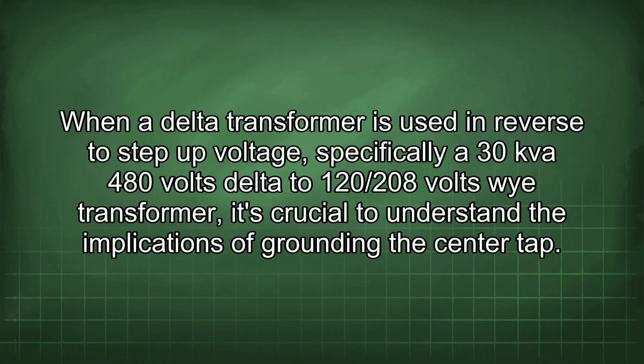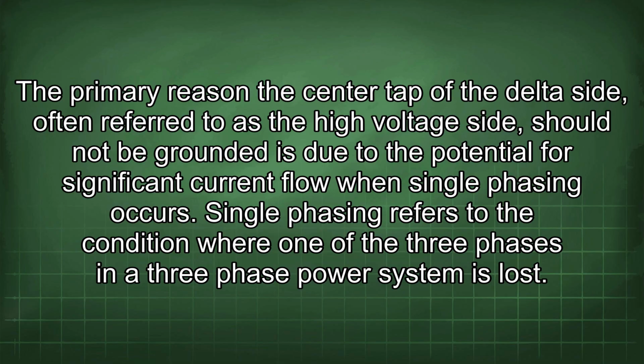When a delta transformer is used in reverse to step up voltage, specifically a 30 kVA 480 volts delta to 120/208 volts Y transformer, it's crucial to understand the implications of grounding the center tap. The primary reason the center tap of the delta side, often referred to as the high voltage side, should not be grounded is due to the potential for significant current flow when single phasing occurs.